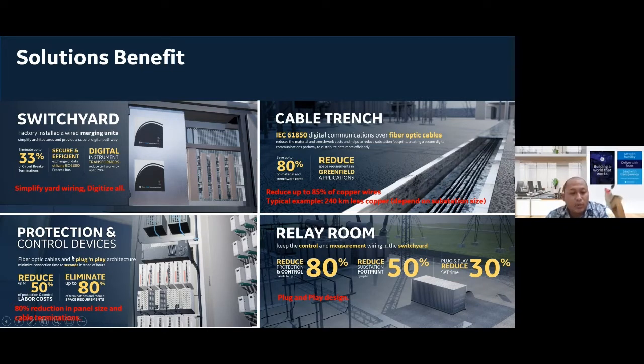On the side of the protection and control devices, it can reduce protection and control labor costs by up to 50%. It can eliminate up to 80% of termination and reduce space requirement. Inside the relay room, ultimately it can reduce the substation footprint by up to 50%, and it can reduce the protection and control panel size by up to 80%. Related to site activity, it can reduce site acceptance test time by up to 30%. So these are all the benefits that we get when we apply the digital substation system in our system. But again, these benefits will depend on the actual conditions, from country to country.